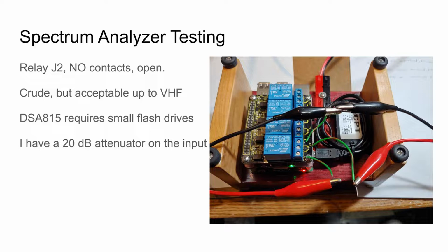I run my SA with a 20 dB attenuator kind of permanently installed on the input. You can correct for that attenuation by pushing the amplitude AMPT button, then changing the ref offset option to 20 dB. In theory, if I accidentally hook up a transmitter and transmit 10 watts into the spectrum analyzer input, that attenuated output would still be within the max input ratings, and transmitting much over 10 watts would probably melt the attenuator off the panel, thus saving the spectrum analyzer, at least optimistically.